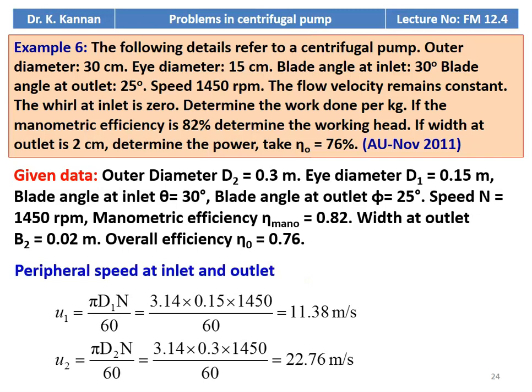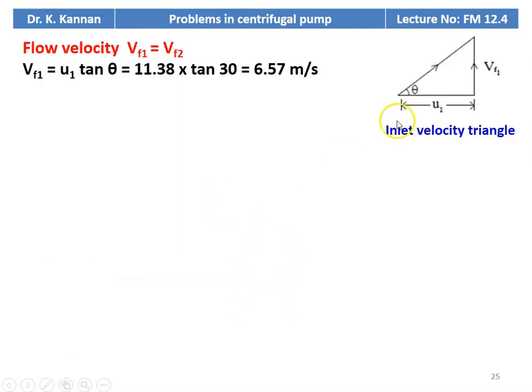We calculate the peripheral speed at the inlet and the outlet. U1 equal to pi D1 N divided by 60, substituting: 3.14 into 0.15 into 1450 divided by 60 equal to 11.38 meters per second. U2 equal to pi D2 N divided by 60: 3.14 into 0.3 into 1450 divided by 60 equal to 22.76 meters per second. From the inlet velocity triangle, flow velocity VF1 equal to U1 tan theta, which is 11.38 into tan 30 equal to 6.57 meters per second.